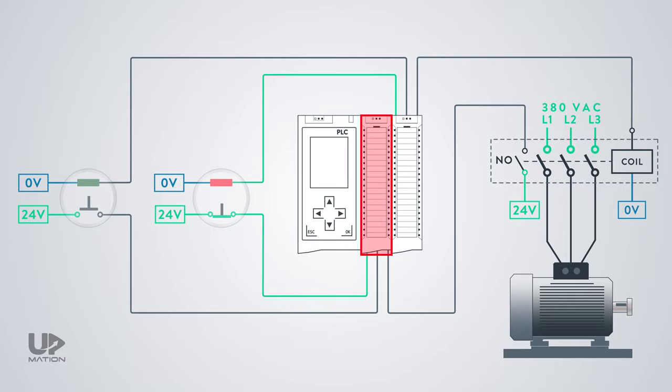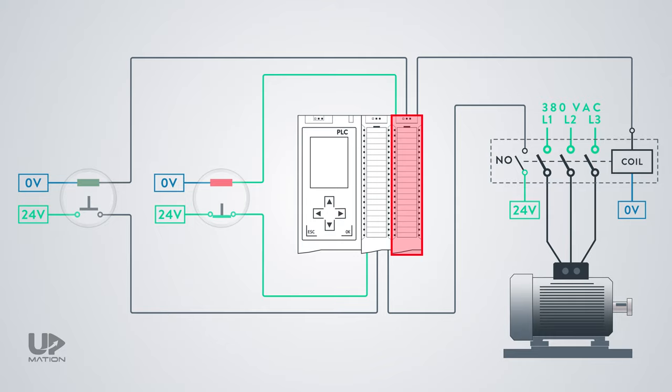And another input from the contactor's auxiliary contact. We use the input from the auxiliary contact of the contactor in our PLC program as the feedback for the electric motor status. Is it on or off? By the way, we have three outputs as well: one for turning on and off the electric motor, and the other two are for turning on and off the indicator lamps of the push buttons.